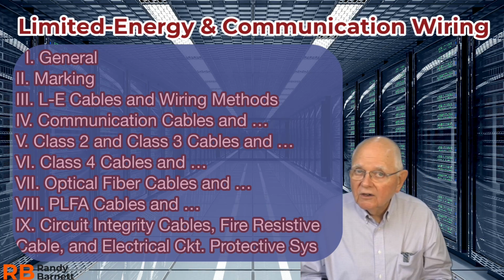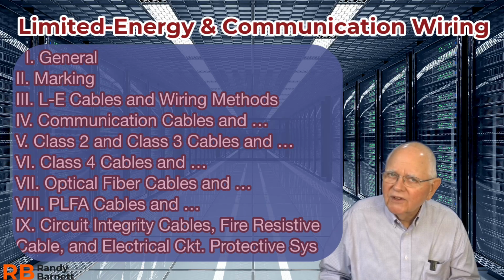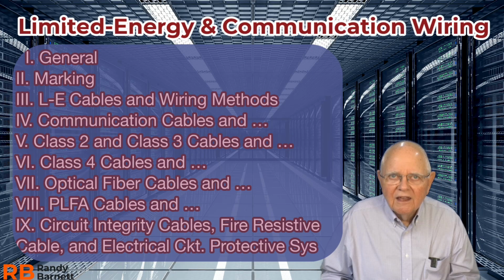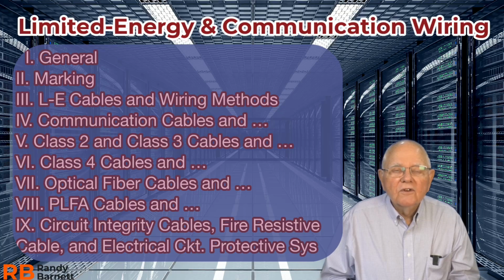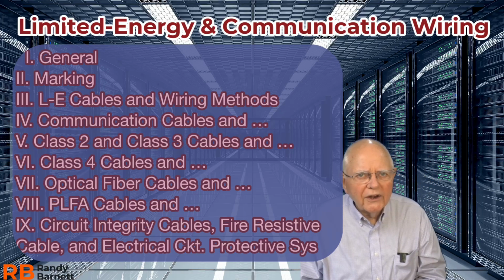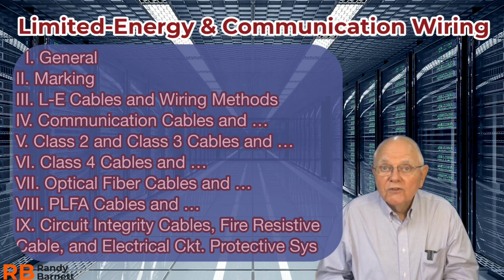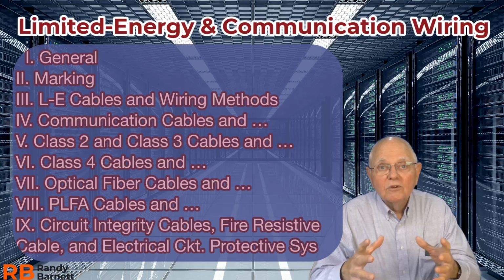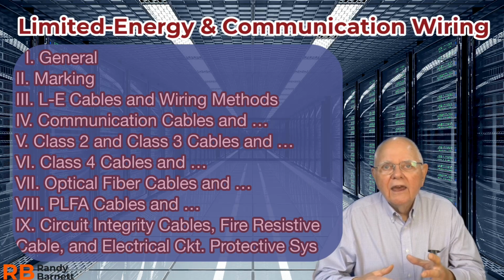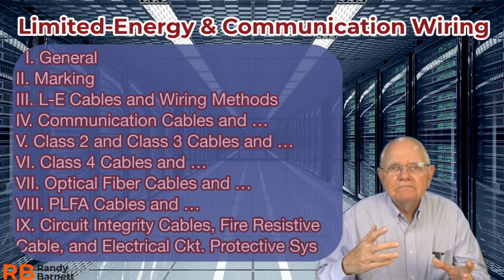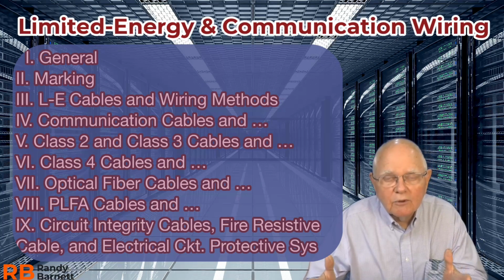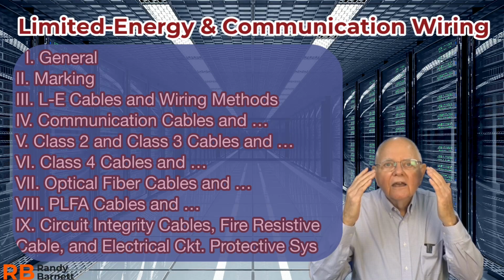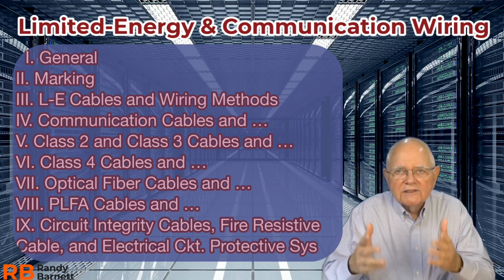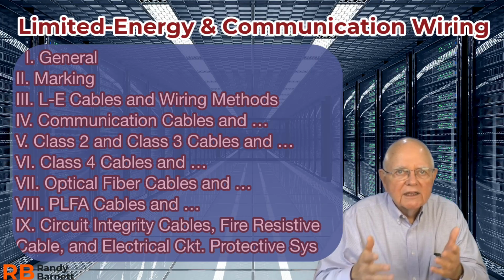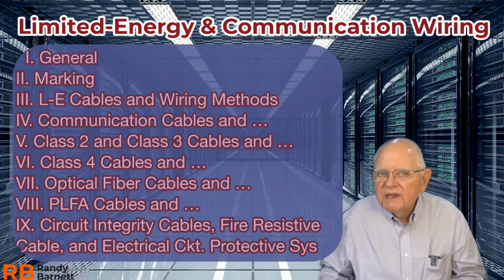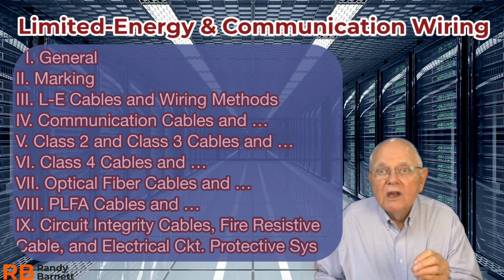That's a lot of stuff in this article. The good news is there are lots of tables that tell you how to apply your articles. So, if we were to take a look, for example, at Table 722.100A, you'll see that the columns are our cables, the application of our cables, and then the different types of cables, okay? And it makes sense. So if I have a Class 2 cable, it tells me that's a general purpose Class 2 cable, and it's marked CL2. CL2P on this table would tell me it's a Class 2 plenum rated cable.